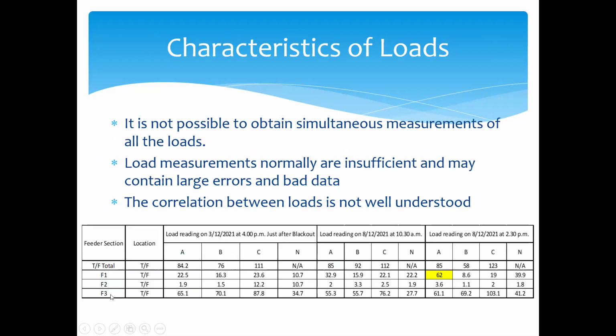And these F1, F2, F3 are feeder currents. That transformer has 3 distribution feeders, and the feeder currents are given here. The transformer total we can get automatically from the installed meter, even from my office computer, for one exact time interval. But to obtain the feeder currents, we have to go to the field and measure the current one by one in the 3 feeders. It may take a few minutes. We have to get the feeder current in R phase, B phase and C phase in one particular feeder, and then climb to the other side of the transformer and get the current of the other feeder. So it consumes several minutes.